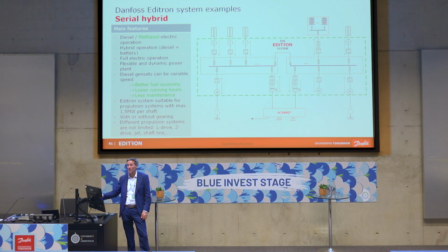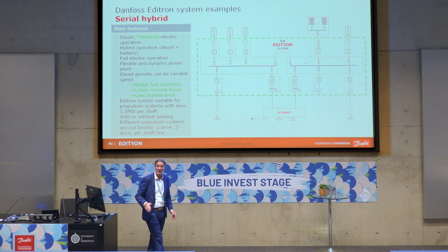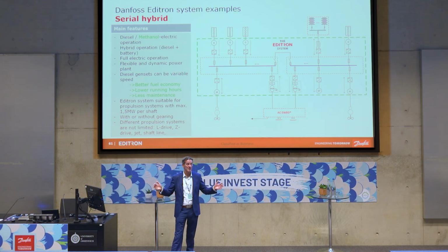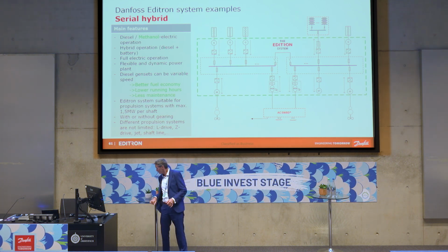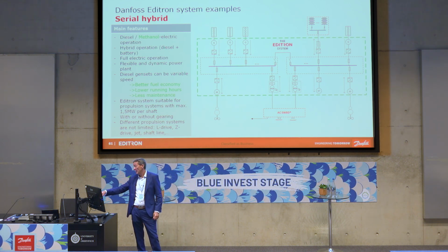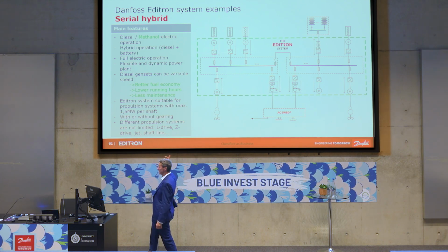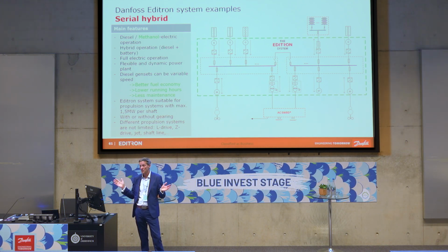Then we distribute that throughout the vessel. Hanging off that DC, on the left-hand side we've got one of the propulsion motors, and on the right-hand side another. We always split the system port and starboard, because we need redundancy - for certification, and also just to be sensible, so we don't take the whole system down if we lose one side. In between, we've got isolation in the middle where we can separate the two sectors, so if there's a problem, we can just open those breakers.